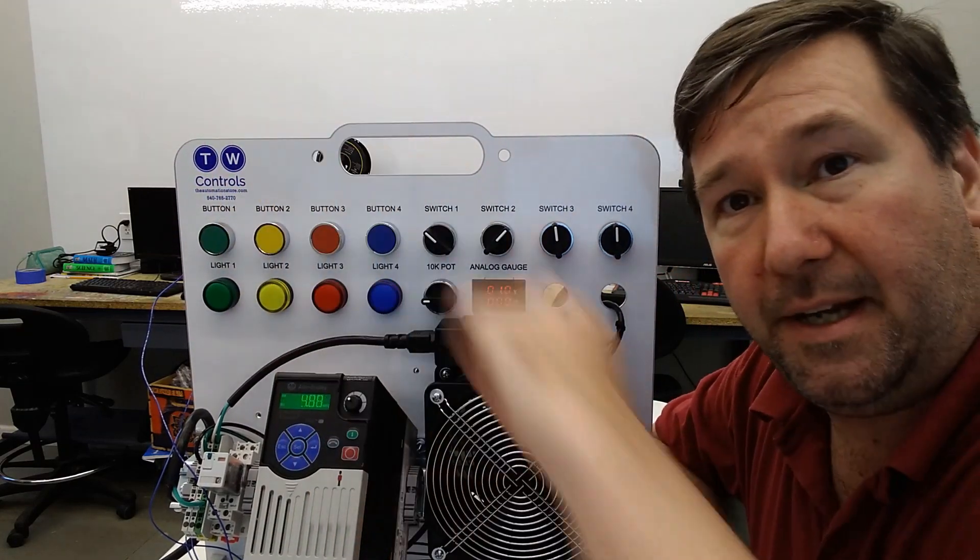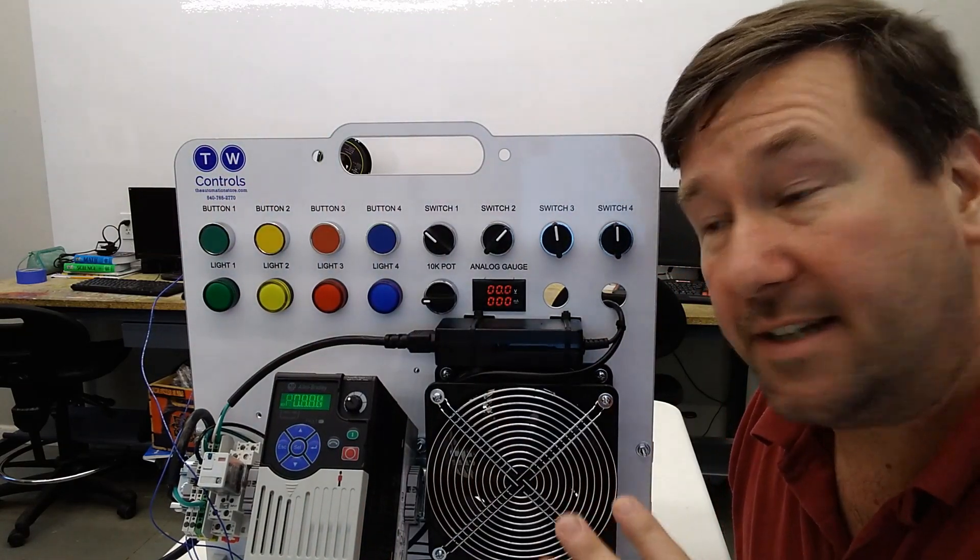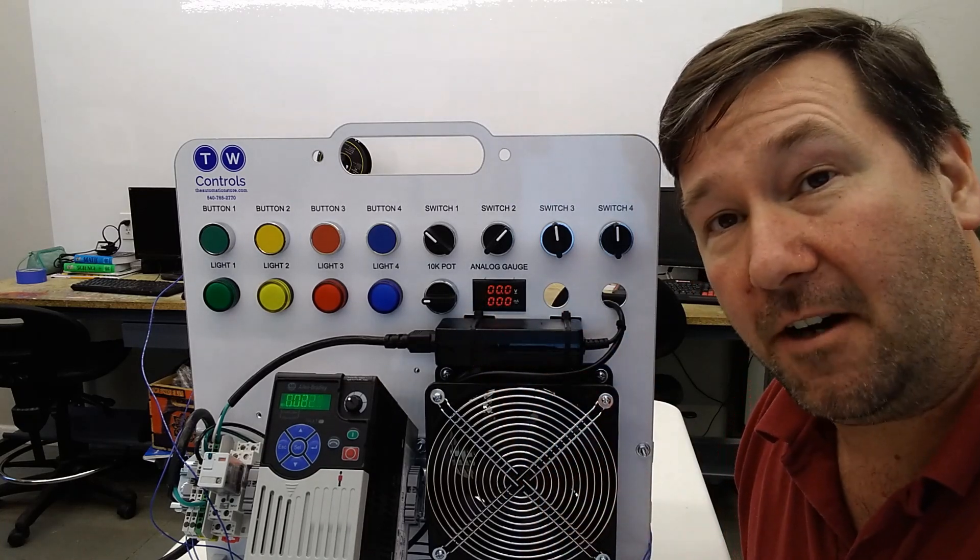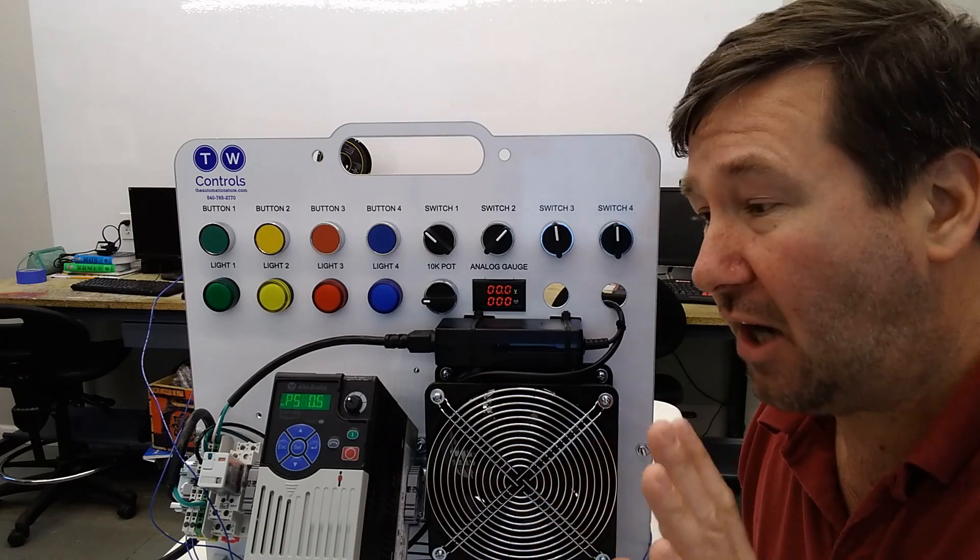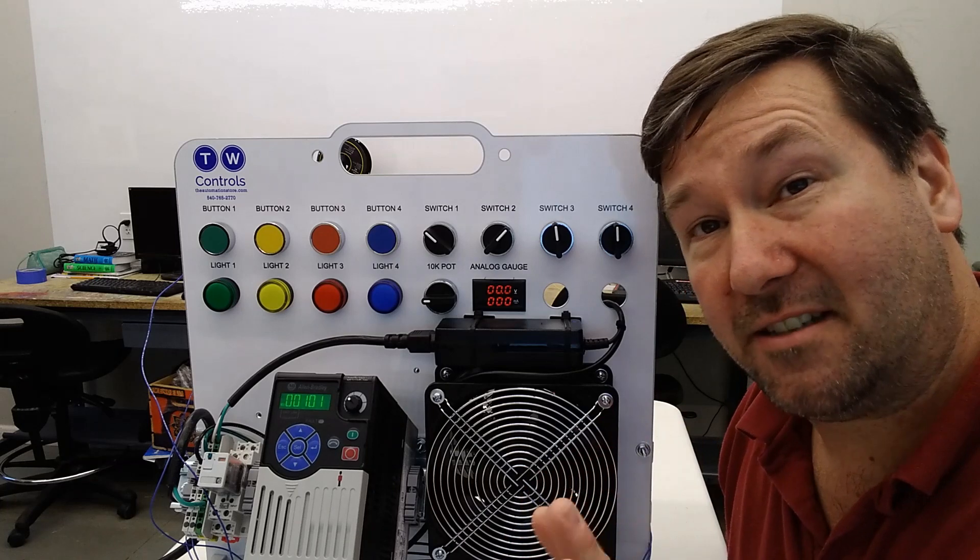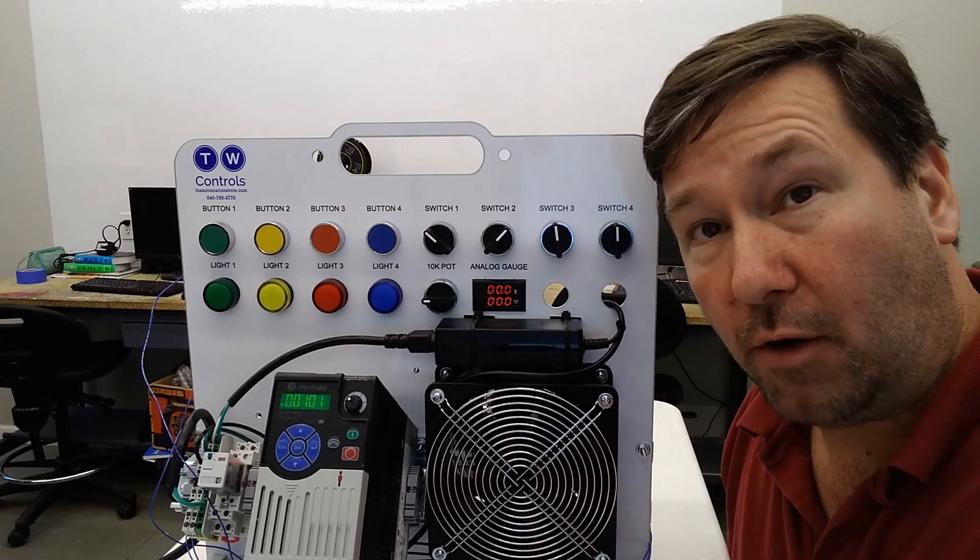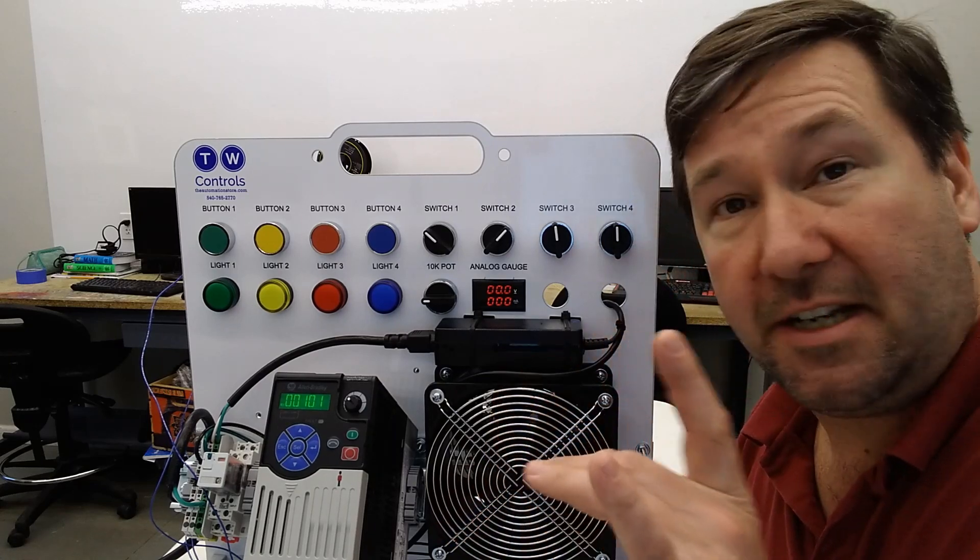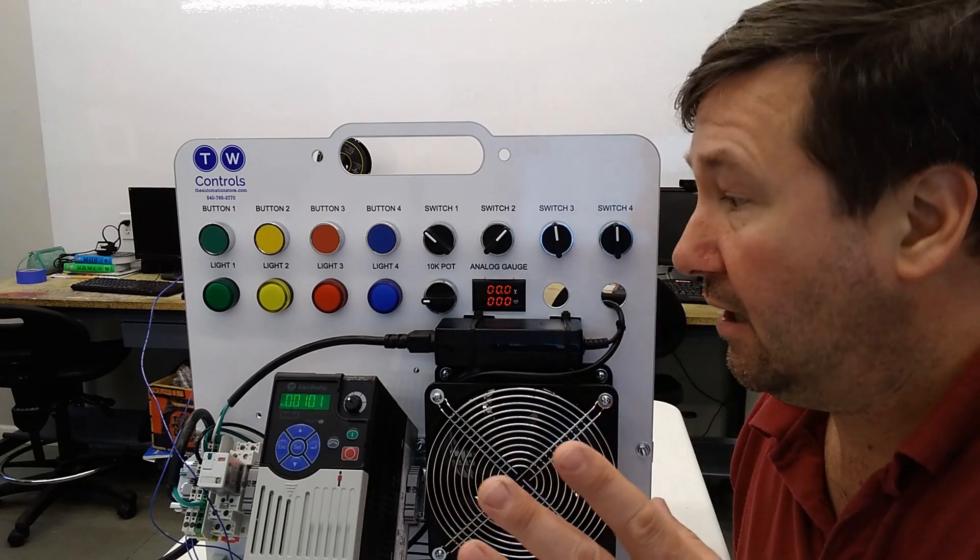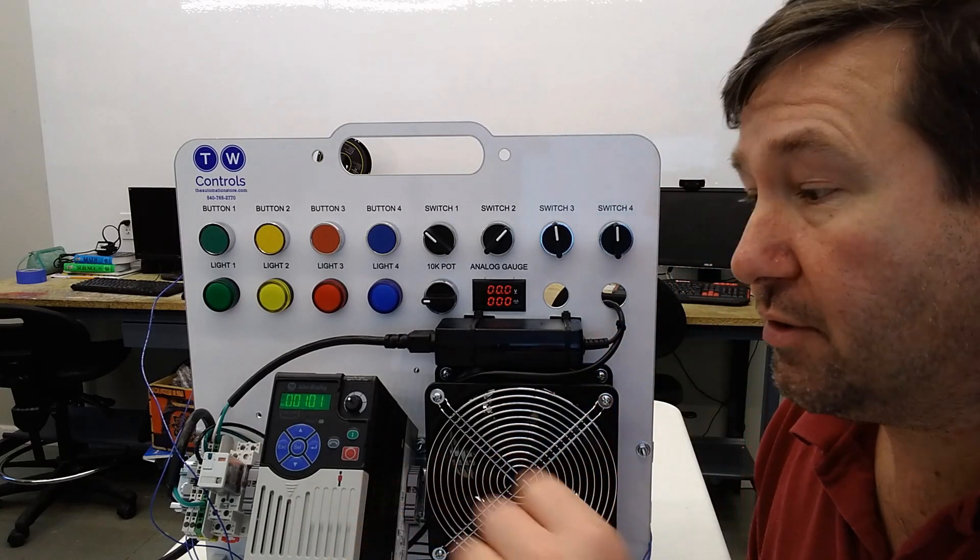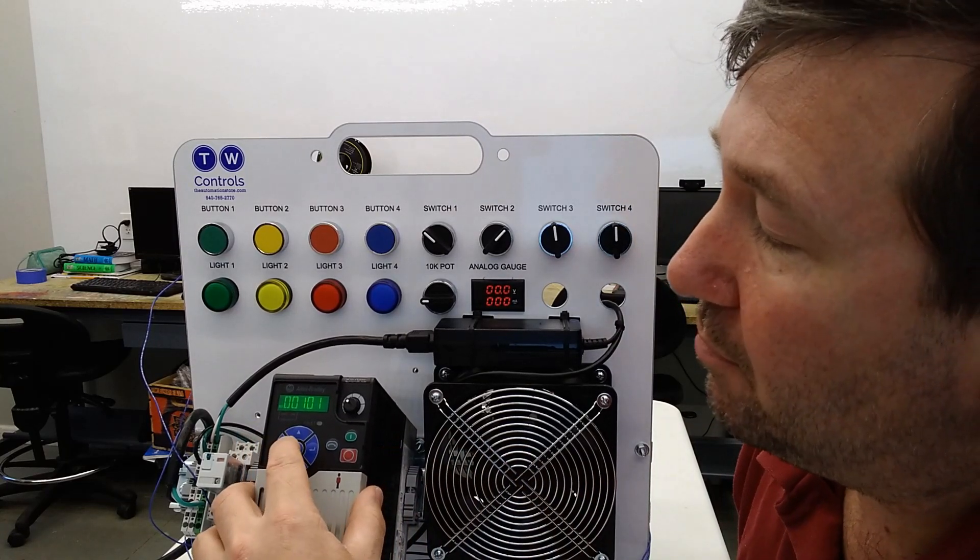All right, let's go ahead and hit the stop button. And let's talk about some of the other ways that you could configure this analog output. Because I told you the default is the output frequency or the drive speed, which is by far the most common thing you would have it on. But there are actually eight different set points that you can have it on for your voltage mode. Most useful, I think, would be it can do output voltage, it can do output amps, it can do kilowatts.